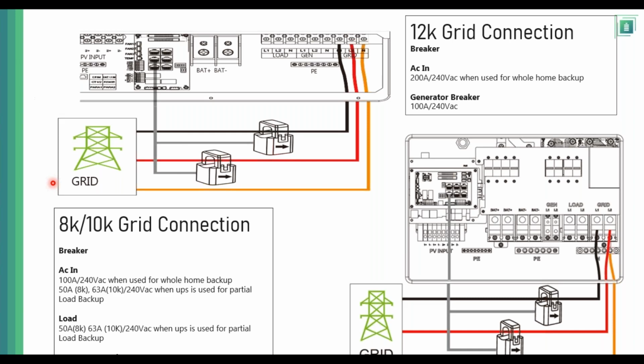Now, if you're doing a partial backup, the CTs would go in between the grid and the main panel, okay? And that is if for some reason the customer wants to do fast zero export, it would take the consumption and provide power to that consumption, right? It's called fast zero export. Basically, I don't want to export to the grid. I just want to provide the necessary power for my loads. Okay, great. So these CTs will measure the power consumption and will allow the system to provide that necessary power without exporting anything.